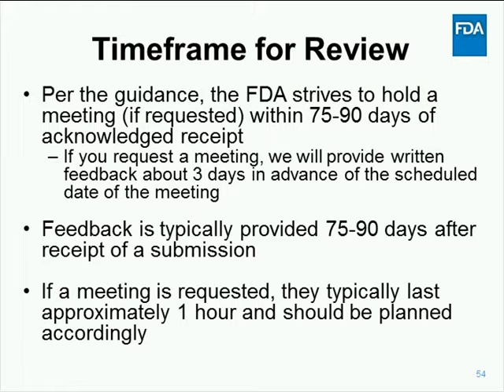The pre-submission guidance outlines the time frames for pre-submission review. If you request to hold a meeting with us, we'll strive to have that meeting within 75 to 90 days of the acknowledged receipt of your pre-submission. We'll aim to provide you with written feedback around 3 days in advance of your scheduled meeting date. After you receive this written feedback, if you have no further questions, you're certainly welcome to cancel the meeting. I'll note that typically we won't be able to have a meeting earlier than that 75-day time frame due to the workload considerations for our review staff. We urge you to budget your meeting time accordingly for a 1-hour meeting, as we're generally unable to hold meetings longer than an hour.